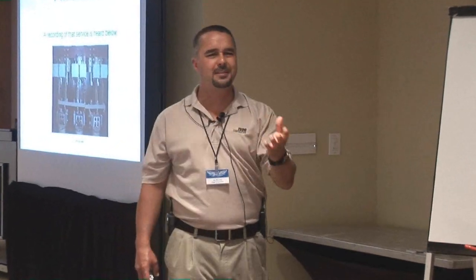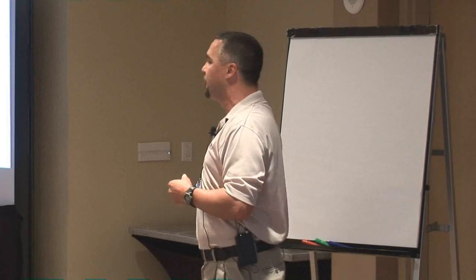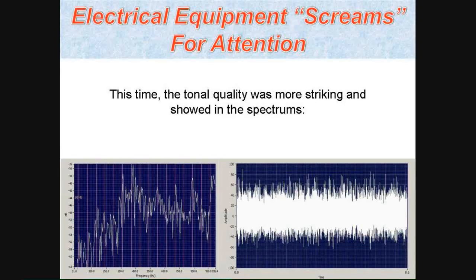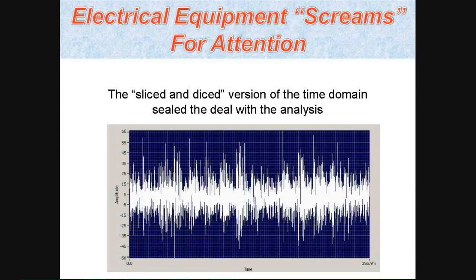And in electrical, the decibel level, unlike motors and bearings that we talked about a little bit earlier, for me with electrical, it's only telling me how close I am to the source of an emission. It's not a gauge for severity on how bad something is. So looking at these spectrums, the FFT, it's got some noise content. There are a couple 60 hertz harmonics. But in the time domain, you can see that the intensity has increased, as well as the frequency of occurrences or discharges. And dicing that up or magnifying it really illustrates that point.